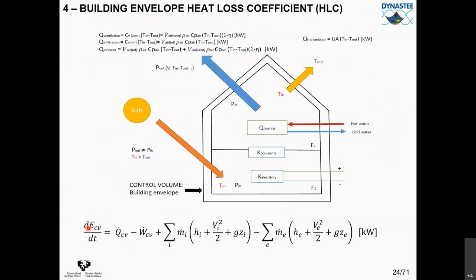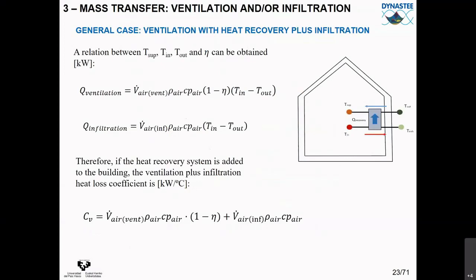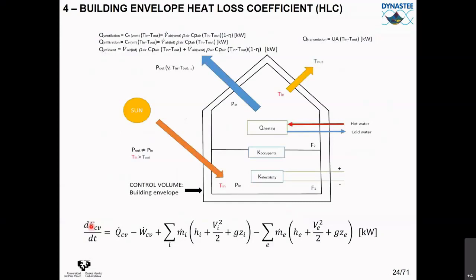For ventilation systems with heat recovery, the outdoor air entering at, say, 5°C is heated by the outgoing air at 20°C. Perhaps the exhaust leaves at 10°C and the supply enters at 15°C — a useful energy saving. Developing the energy conservation equations gives the ventilation heat loss coefficient as: volumetric airflow multiplied by air density multiplied by specific heat multiplied by (1 minus the efficiency of the heat recovery device). If efficiency is perfect, 1 minus 1 equals zero — no heat demand due to ventilation. Adding the ventilation and infiltration heat loss coefficients gives the total ventilation plus infiltration heat loss coefficient. These two values, UA and CV, are the main characteristics of the building envelope to be identified.